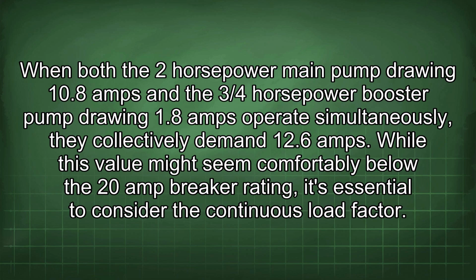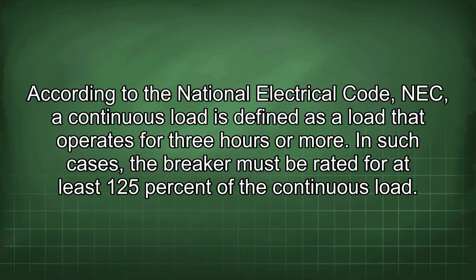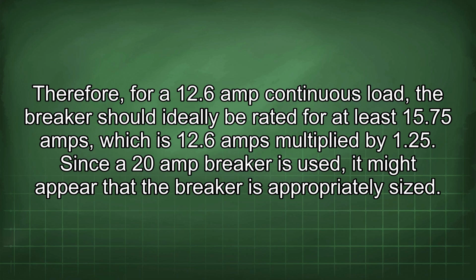While this value might seem comfortably below the 20 amp breaker rating, it's essential to consider the continuous load factor. According to the National Electrical Code, NEC, a continuous load is defined as a load that operates for 3 hours or more. In such cases, the breaker must be rated for at least 125% of the continuous load. Therefore, for a 12.6 amp continuous load, the breaker should ideally be rated for at least 15.75 amps, which is 12.6 amps multiplied by 1.25.